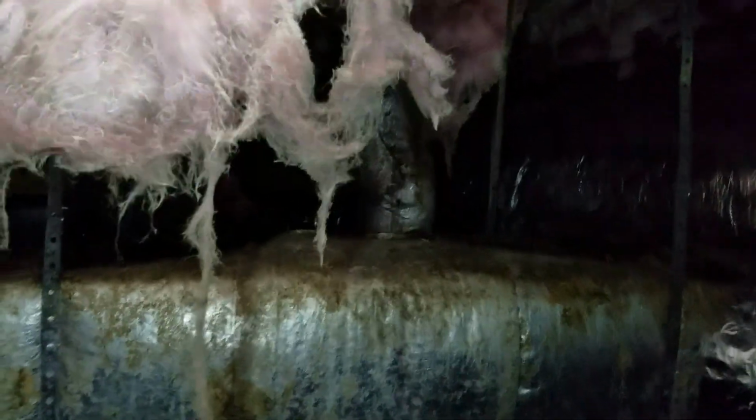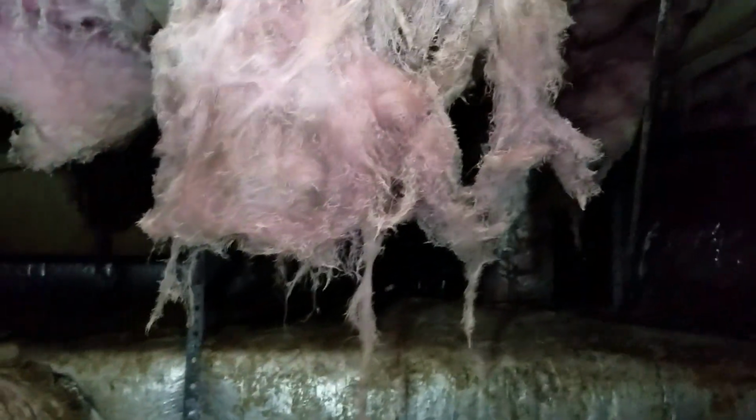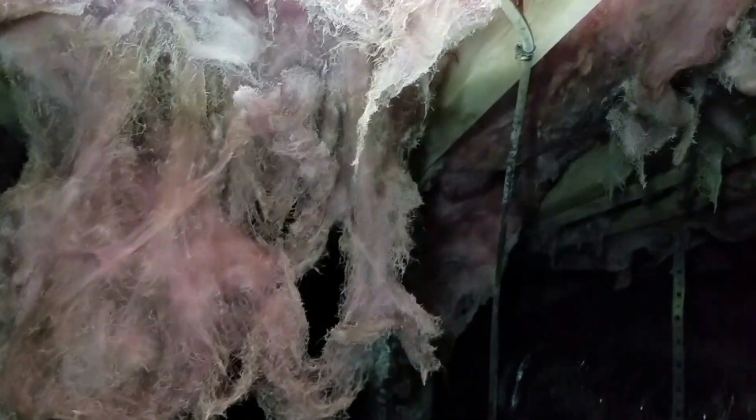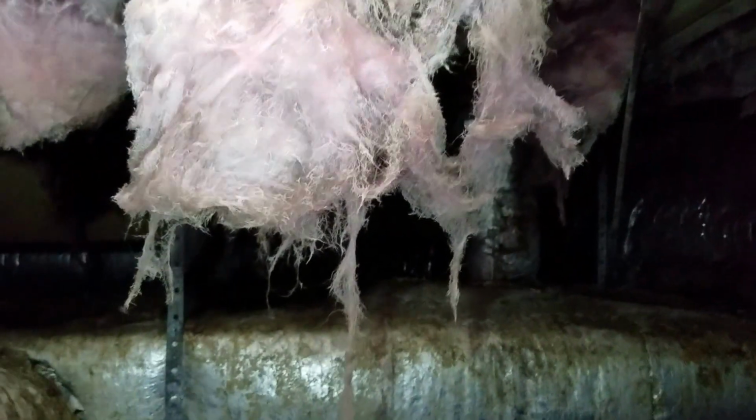Over time, fiberglass insulation will begin to fall. Mold doesn't necessarily grow in the insulation. What has to happen for mold to grow in the insulation is there has to be some type of dust buildup. The mold doesn't grow on the fiberglass, but you have a fiberglass insulation that's full of vacuous air spaces that seem to collect dust. And what happens is you will have mold that begins to grow on those dust collections.